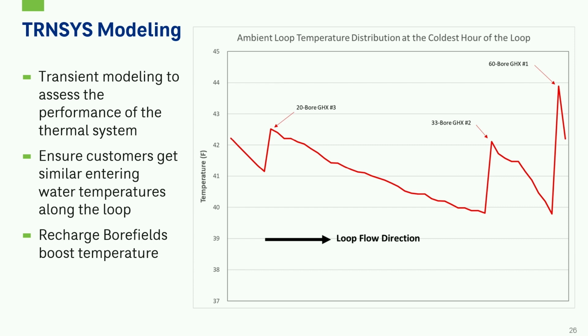which was able to model our ambient loop, the bore fields, and the building connections and what kind of heat pump they were using. So we use this to ensure that all customers along the loop would be able to receive a similar entering water temperature to provide adequate heating and cooling with similar efficiencies to their neighbors. So we didn't want this to be one big loop where someone further down the line was getting much lower entering water temperature than someone right next to the bore field, and then their heat pump would be operating at a different efficiency and they'd have unequal electricity bills to run the same piece of equipment.